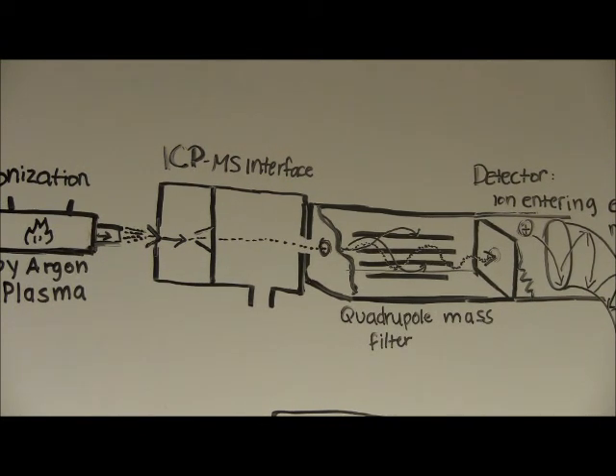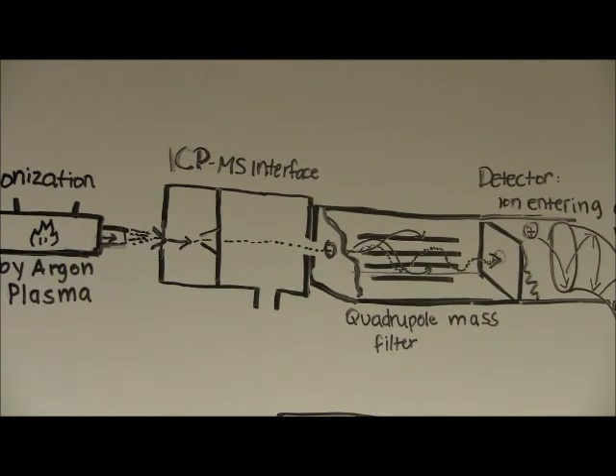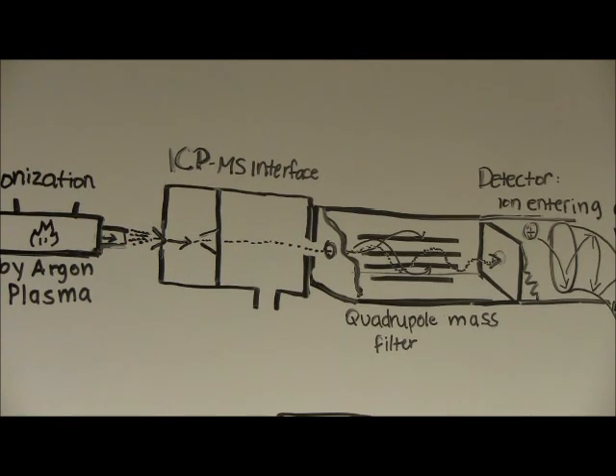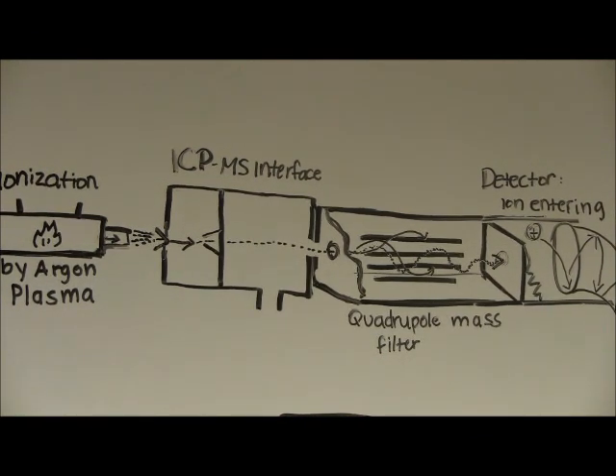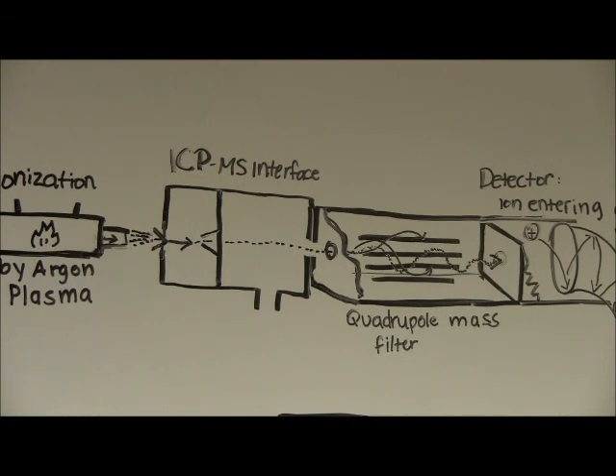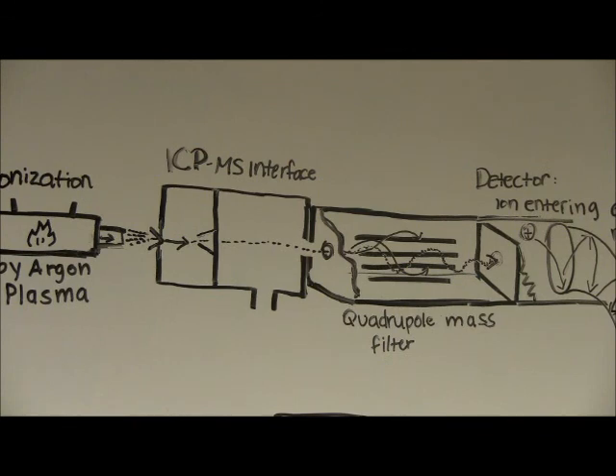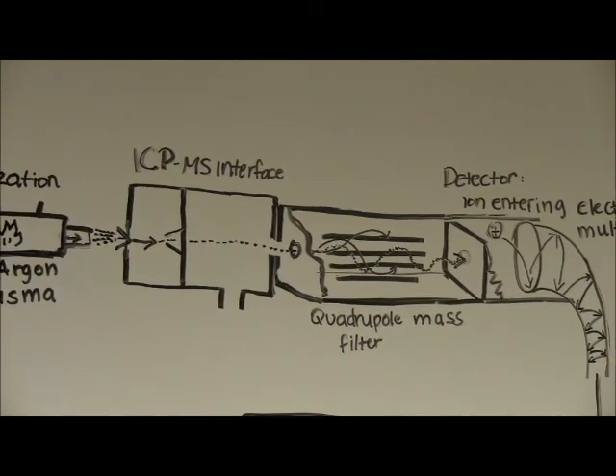In the first stage of the mass spectrometer, ions are removed from the plasma by a pumped extraction system. An ion beam is produced and further focused into the actual unit. There are several different types of mass analyzers which can be employed to separate isotopes based on their mass-charge ratio. Quadrupole analyzers are compact and easy to use but offer lower resolution when dealing with ions of the same mass-charge ratio. Double focusing sector analyzers offer better resolution but are larger and have higher capital costs.